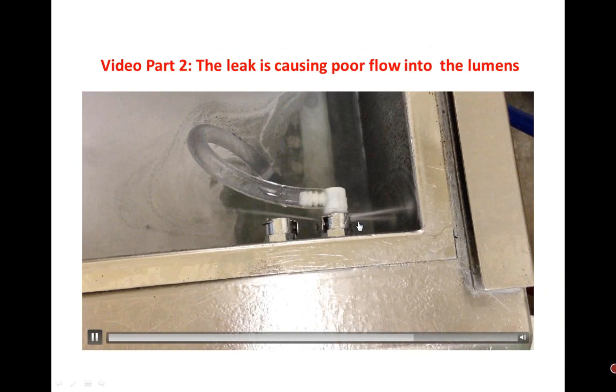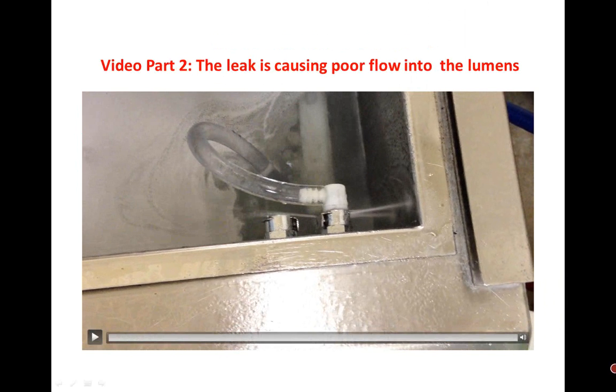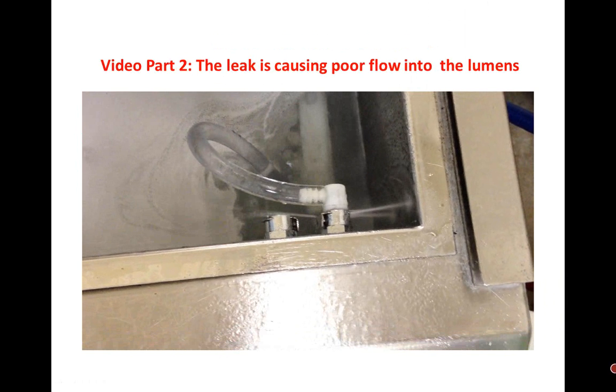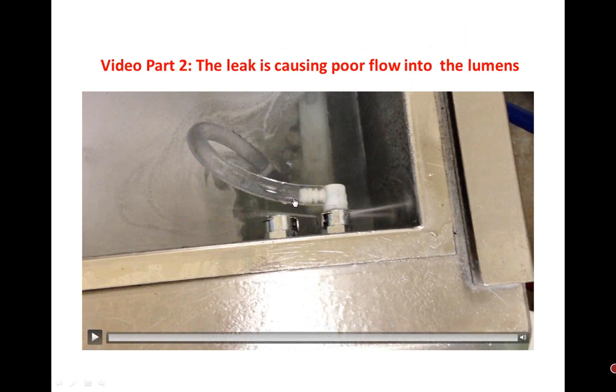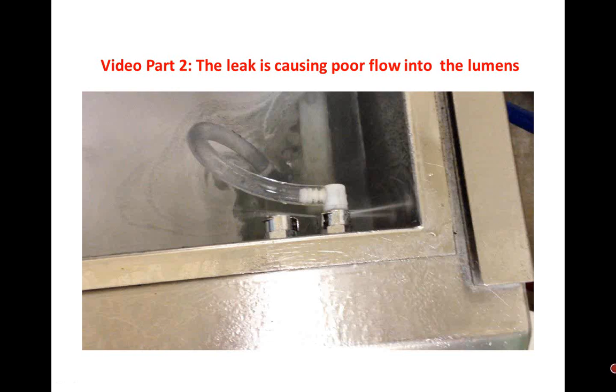Watch right here. Unfortunately, with this machine, you shouldn't be able to open the top. Just so you know, the preventive maintenance was horrible. Notice the water coming from the connector here, and nothing's going through. I hooked up our device called a Lumen Check. It opened up, and it wasn't clean at all, nothing was going through. This confirmed to the staff that something was wrong, and it turned out to be a bad connector. That's why you trust but verify.